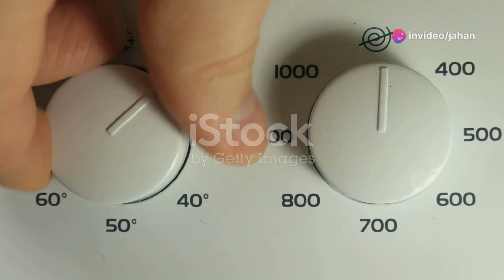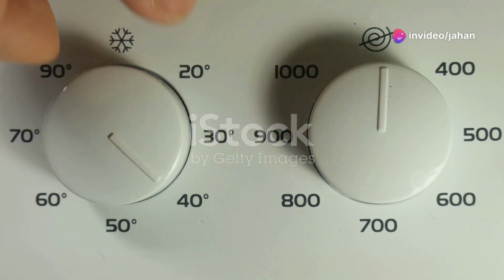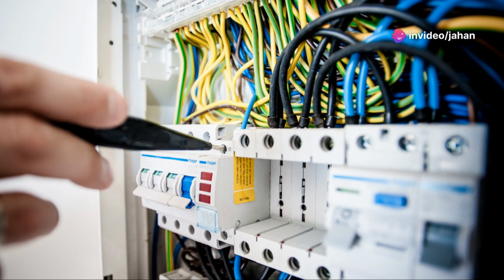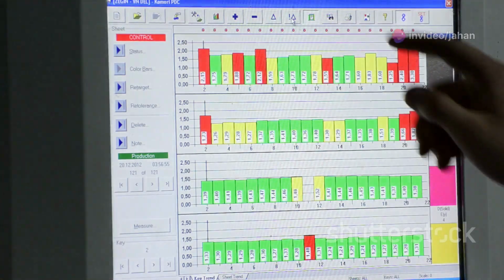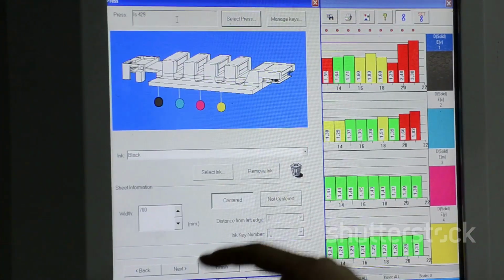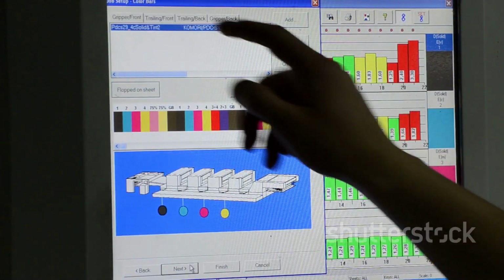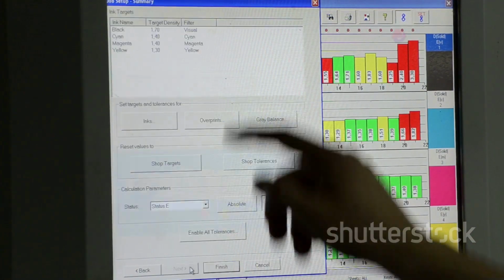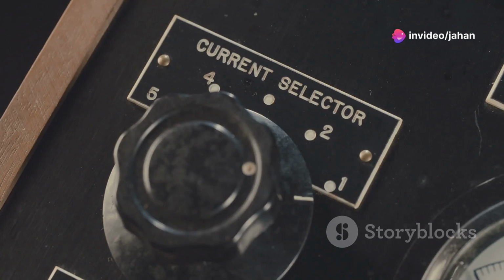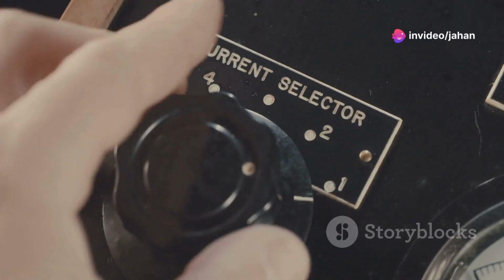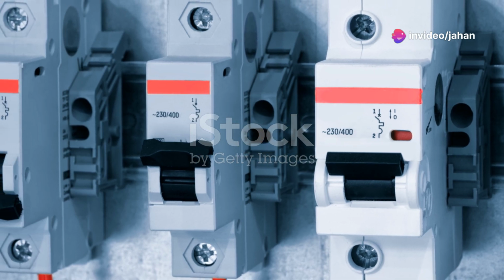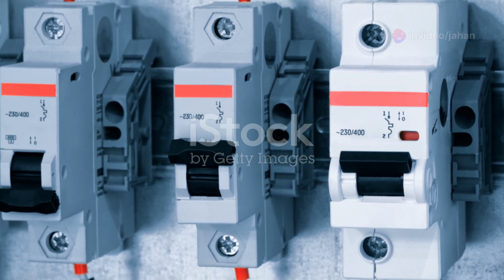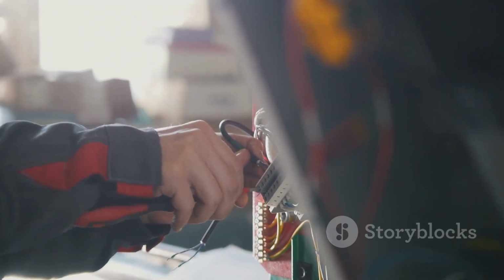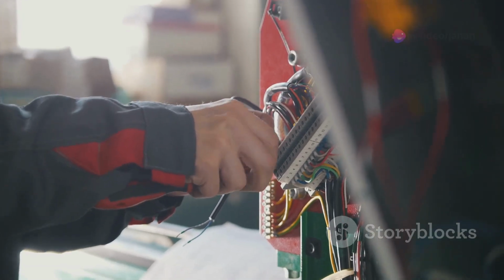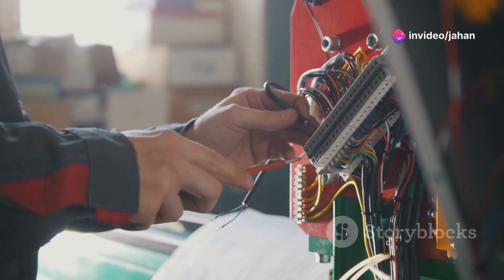Section 6, fine-tuning protection: adjustable settings in ACBs. Now here's where things get really interesting. ACBs aren't just simple on-off switches—they're highly sophisticated devices with adjustable settings that allow for precise control and protection. One of the key adjustable parameters is the overload current setting. Remember how we talked about overloads happening when the current exceeds a circuit's limit?